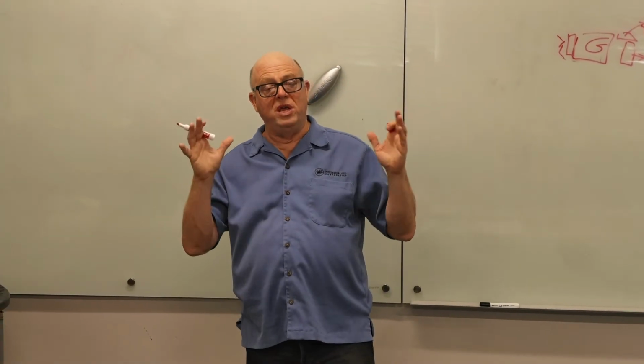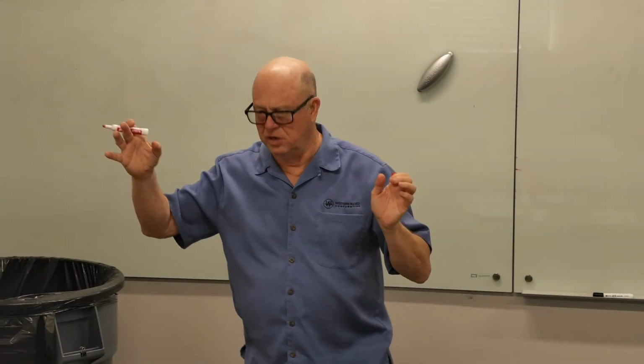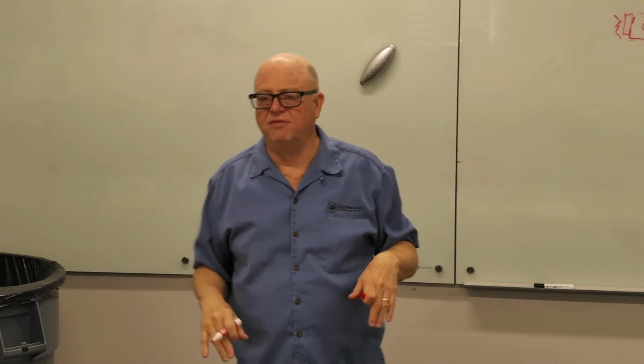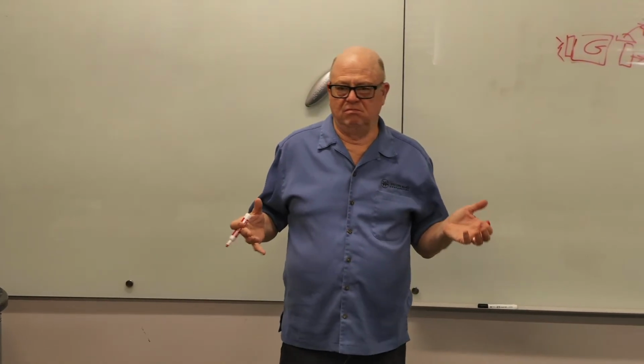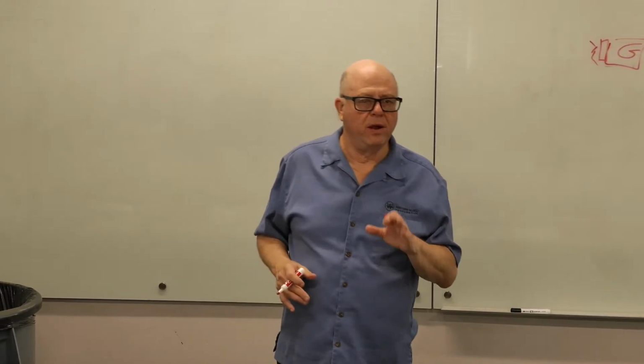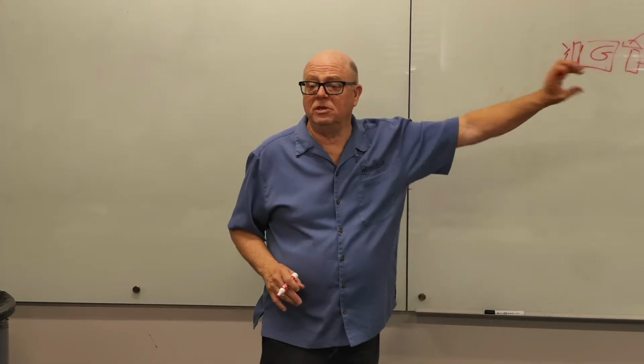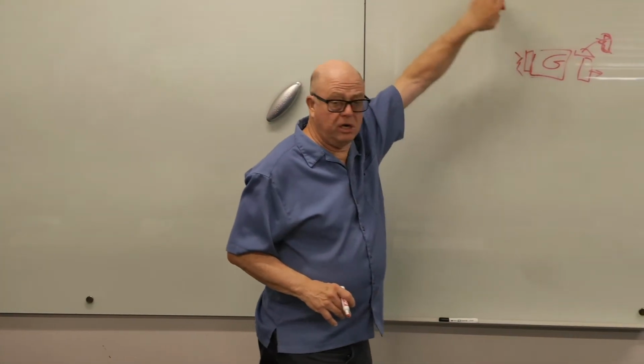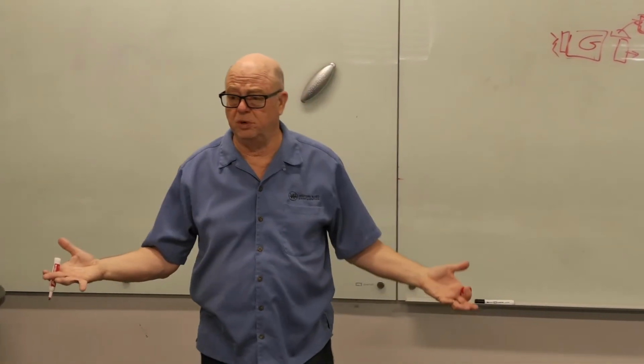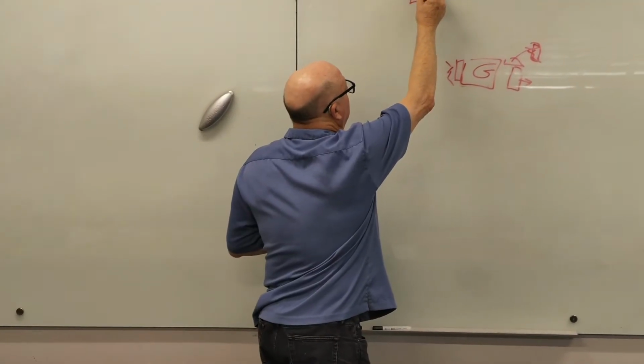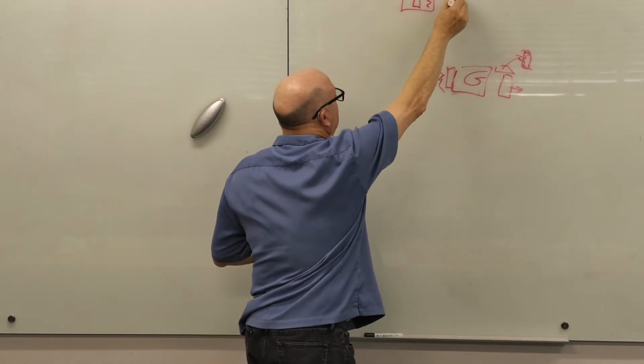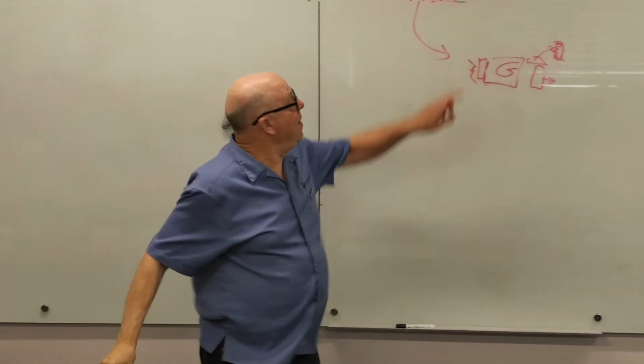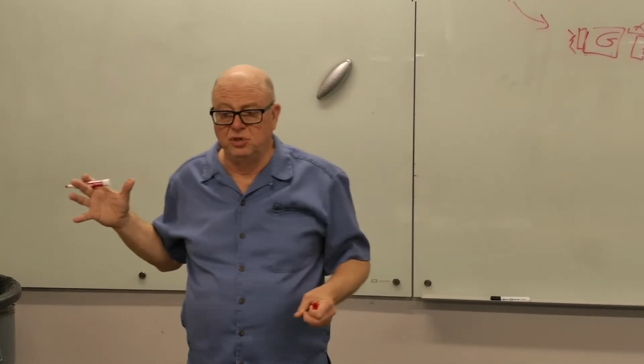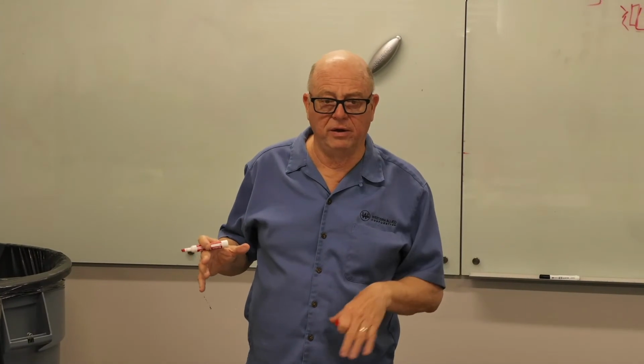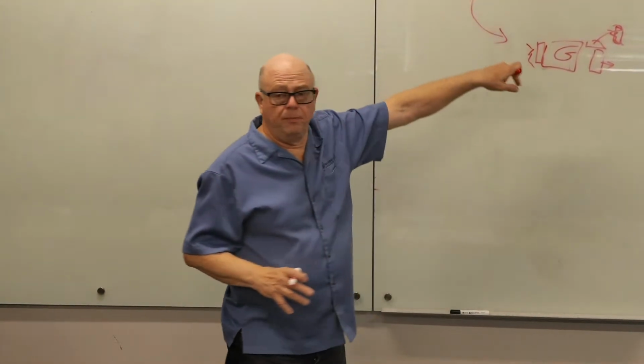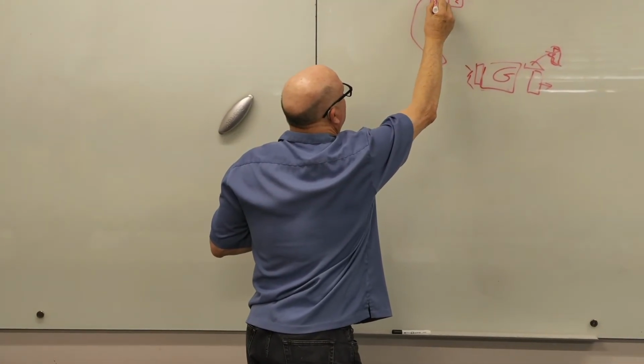We went 3 solid weeks in early July, or very last day of June into July, where it was between 76 and 78 wet bulb peak every day. I mean, this is like Midwest humidity. It was bizarre. Okay? But when you've got to control humidity level in a surgery suite, and you've got a fair amount of outside air, because there's requirements for that in a surgery suite, medical requirements, we ended up wanting to put in a cooling coil and a filter, 100% outside air, and bring that down, and pre-cool, basically knock some of the moisture. And we'll talk about coils and doing that here a little bit later today. But we wanted to pre-cool. Well, so this is an ECM motor.